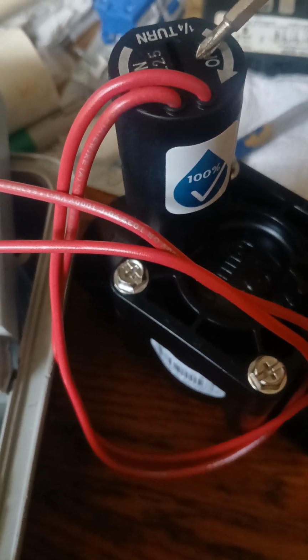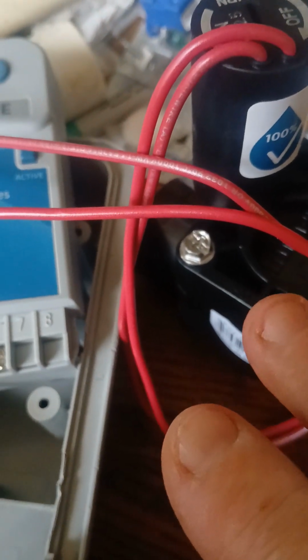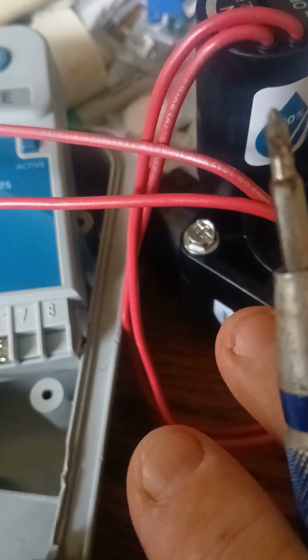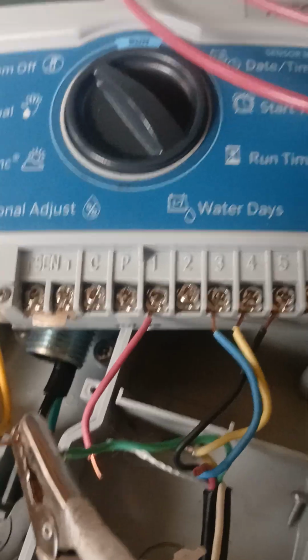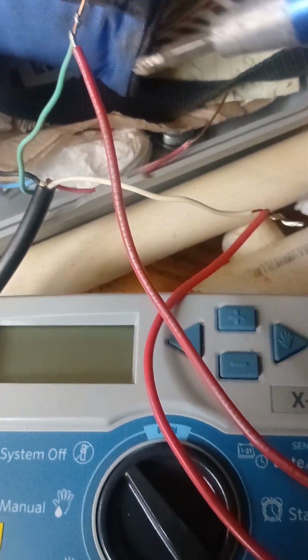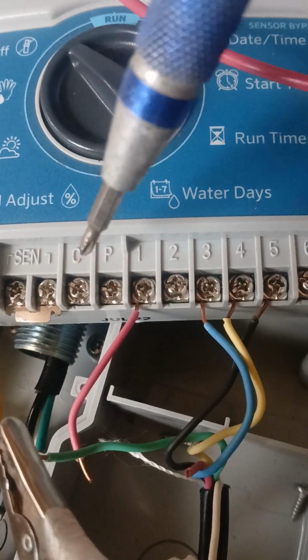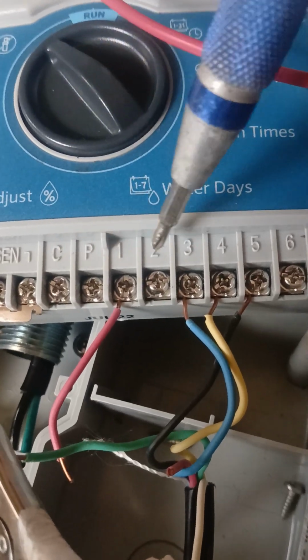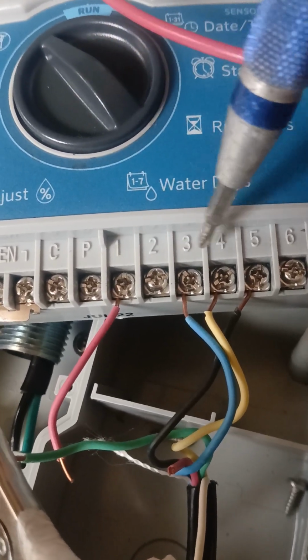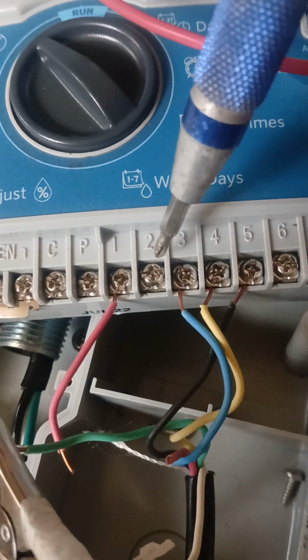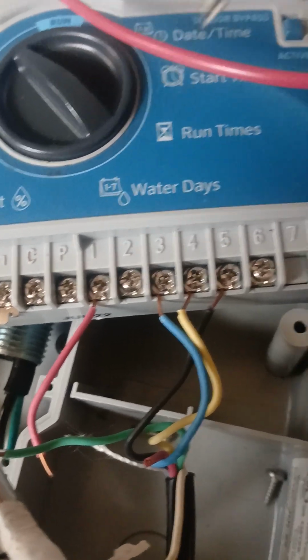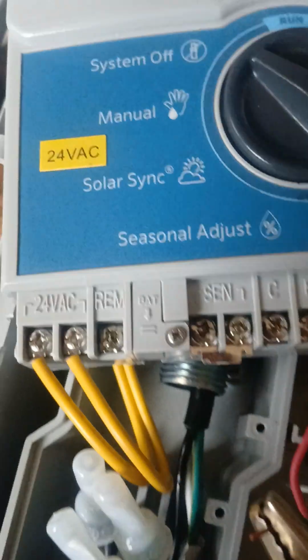Okay, so the question here is, say hypothetically, if we wanted to test the solenoid to determine if the solenoid was good or bad. This is a new solenoid, so hopefully in this case it would test good. What we've done is tied the wires together. We've removed the wires here, the common here, and we removed number 2. It could be number 1, 3, or 4. That doesn't matter, whichever zone you want to test. Say hypothetically this was on zone 2, so we're testing zone 2 to see if the solenoid's good.